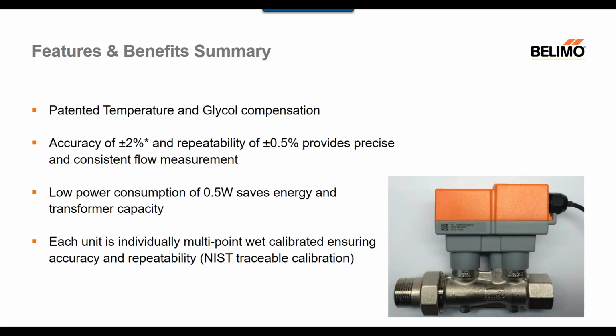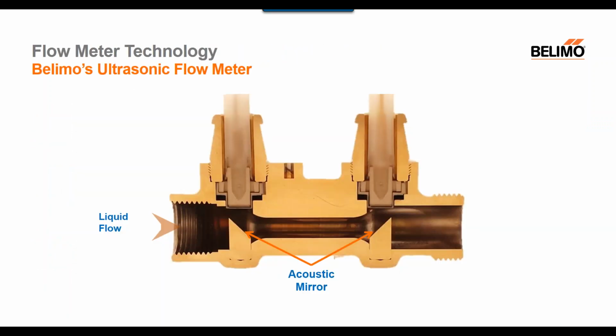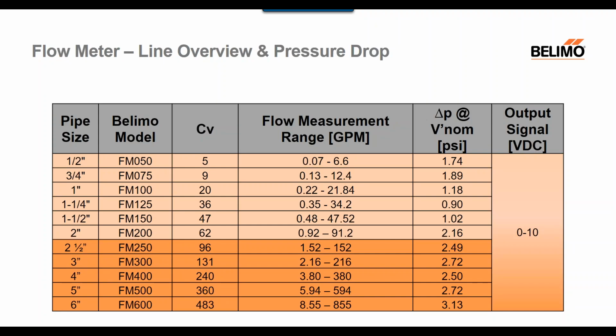Yes, the CV value does change, and if you want, I can go back to the previous slide and show the different CV values with reference to the flow measurement ranges. Here we see the 1/2 inch at 5 with the flow range 0.07 to 6.6 GPM, and for example, on the larger size, the 6 inch, we would see the CV value of 483 and a flow range of 8.55 to 855.